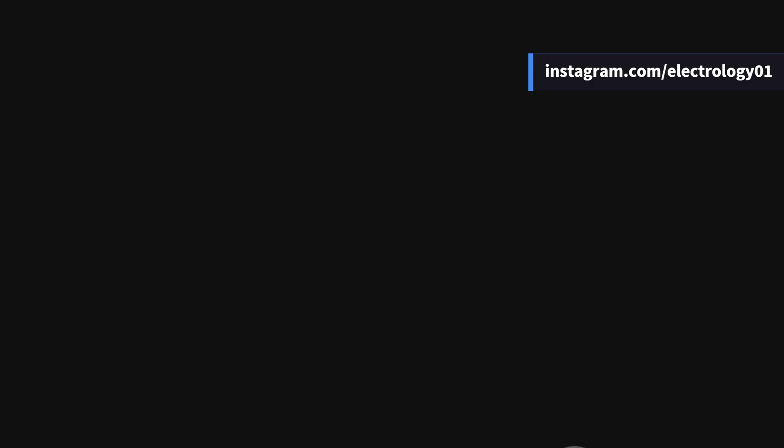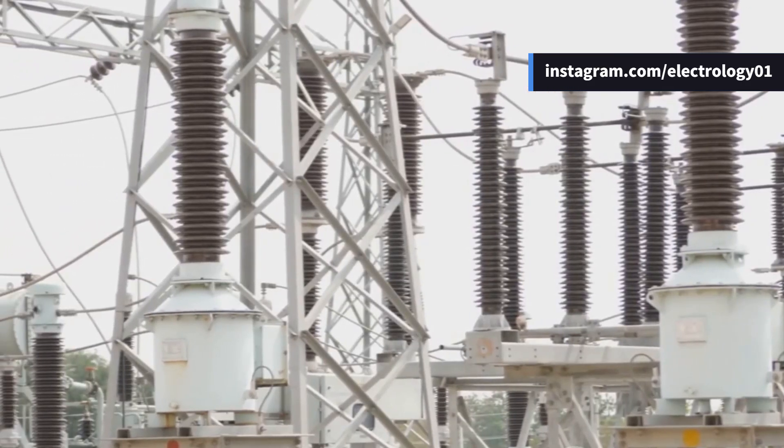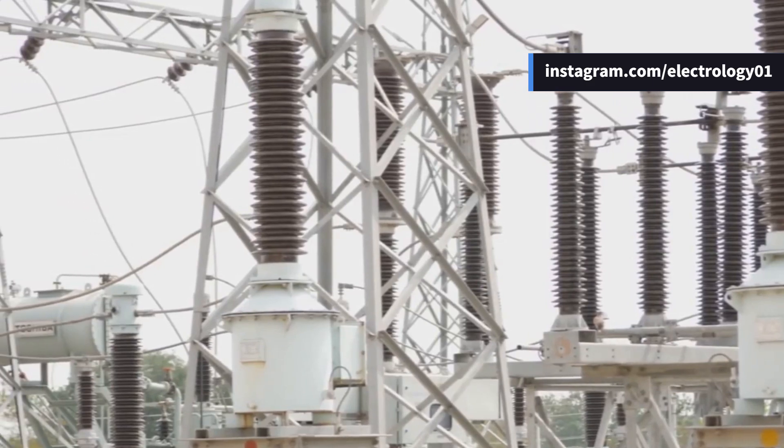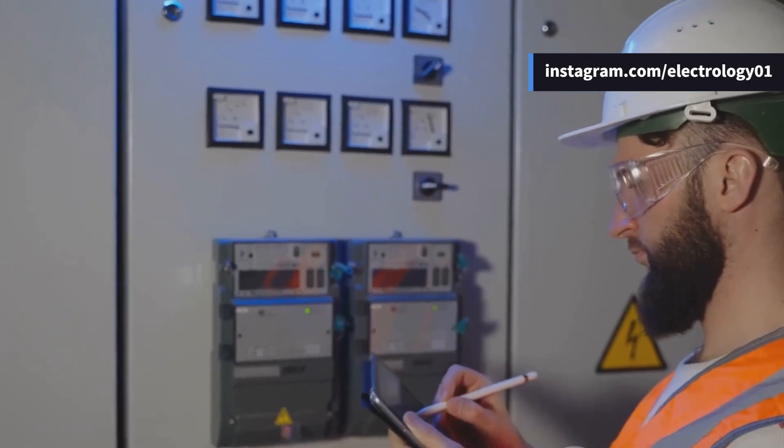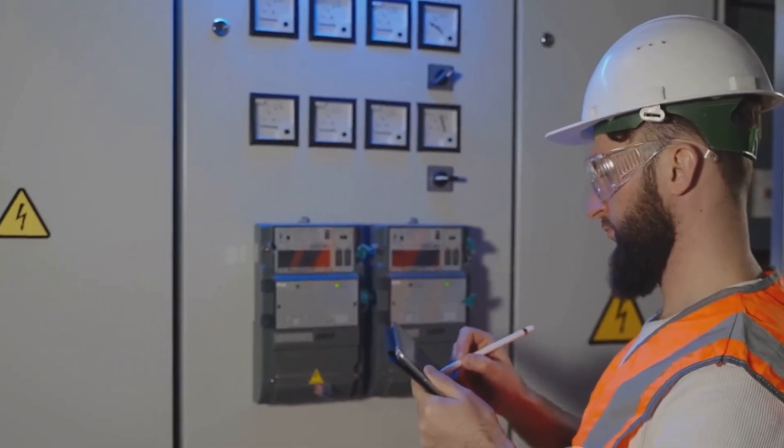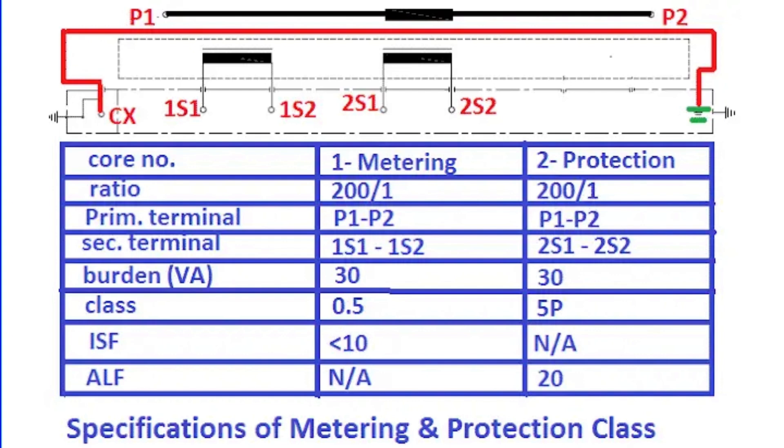Current transformers or CTs are an integral part of power systems. They are broadly categorized into two types based on their application: metering CTs designed for accurate measurement during normal operating conditions, and protection CTs designed to operate accurately during fault conditions. Each type of CT serves a unique purpose and using one in place of the other can have serious consequences.